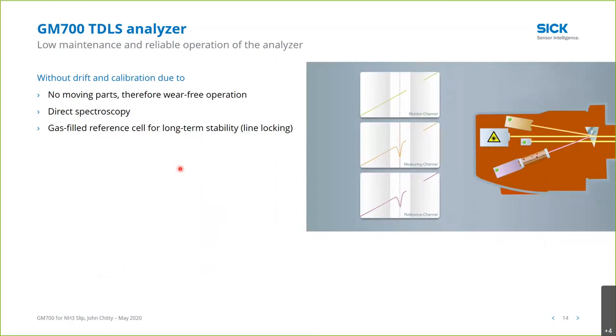So there's no moving parts. Therefore, it's wear-free. It's a direct spectroscopy. And that gas-filled reference cell is for long-term stability and provides line locking. Line locking is something that happens with laser type analyzers. They can drift off of the spectral line that they're supposed to measure. So with each scan, we check that reference to make sure that we're looking at the right line. I lost my cursor.